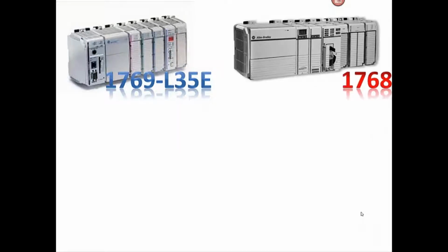Then we're also going to add a 1768 L45. This is the newer, but not the newest family of CompactLogix. There's actually 3 basic families: 1769, 1768, and then a newer one that I call L1, L2, L3. They are supported only on version 21 and higher of RSLogix 5000. These two families of the CompactLogix platform are supported by the earlier versions of RSLogix 5000.